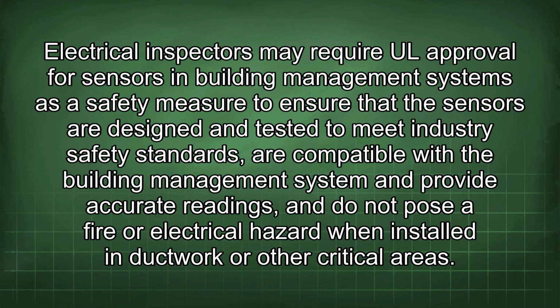Electrical inspectors may require UL approval for sensors in building management systems as a safety measure to ensure that the sensors are designed and tested to meet industry safety standards, are compatible with the building management system and provide accurate readings, and do not pose a fire or electrical hazard when installed in ductwork or other critical areas.